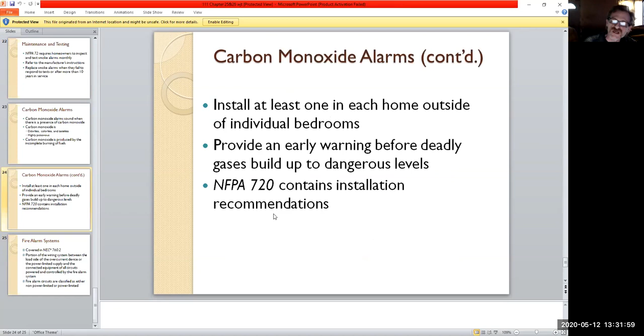It does have different installation recommendations than smoke alarms, because you have to look at where the gas is going to be coming from. Generally, it's anywhere you're going to ignite—so if you have a gas burning stove in the kitchen, a gas burning furnace in your utility room or crawl space, or the same with the hot water tank, you're going to follow that through. NEC covers that, and NFPA 720 is a different one that covers basically all types of smoke alarms, heat alarms, and carbon monoxide detectors, with proper installations and pretty good pictures too.